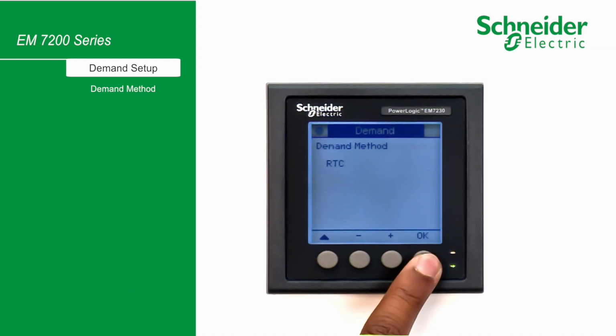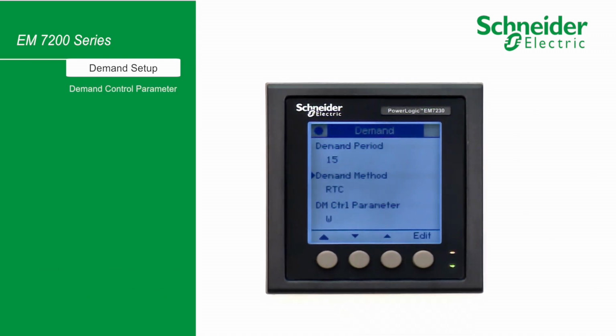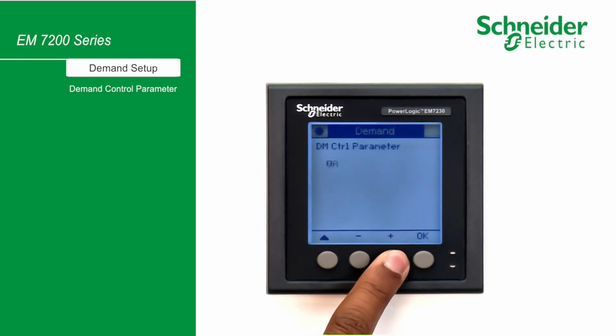Press OK. Your demand controller has the option of selecting different demand computing parameters: active power, apparent power, and three-phase current average. Please note that VARH is not an option for demand controlling, although you can view the demand computation in the meter display. Let's select VA, then press OK.